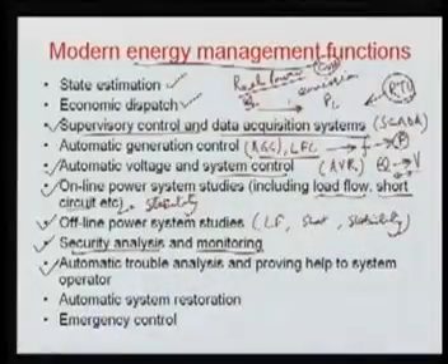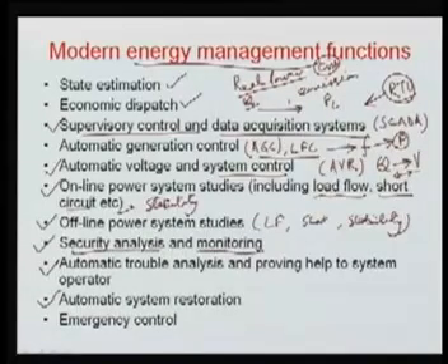Another is your automatic system restoration. We know some parts of the system may be out due to various faults and various other contingencies in the system. So we require the system restoration process. Again, suppose your system is completely in blackout, what will happen? Then you have to light up your generators, because in a blackout your generators have gone and transmission lines are tripped. So you have to start from one end so that you can synchronize your grid as quickly as possible.